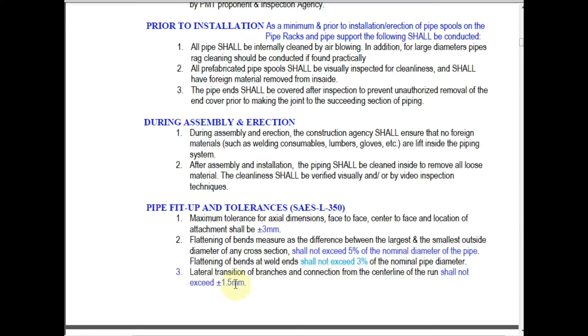3. Lateral transition of branches and connections from the centerline of the run shall not exceed plus or minus 1.5 mm. 4. Rotation of flanges, measured as the offset between elevation of bolt holes on opposite sides of the flange centerline, shall not exceed plus or minus 2.4 mm. 5. The tilt of a flange measured at the periphery across any diameter shall not exceed 1.6 mm from the square position.